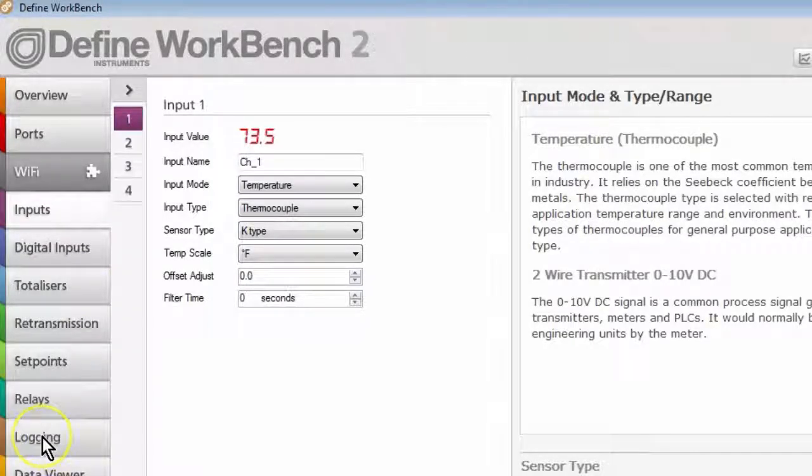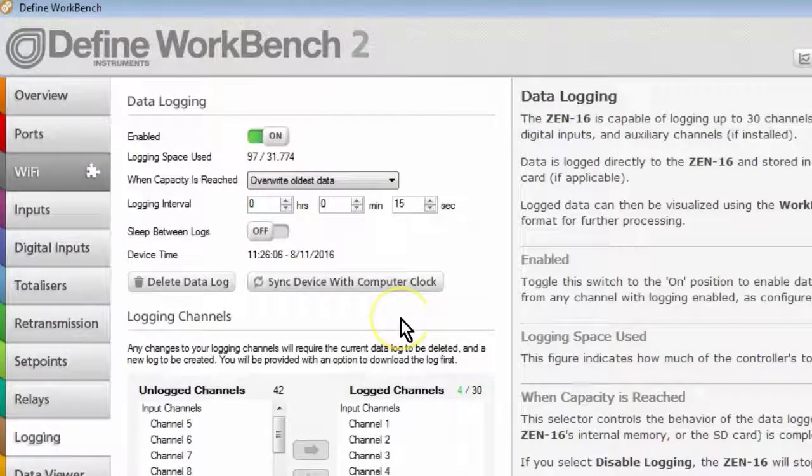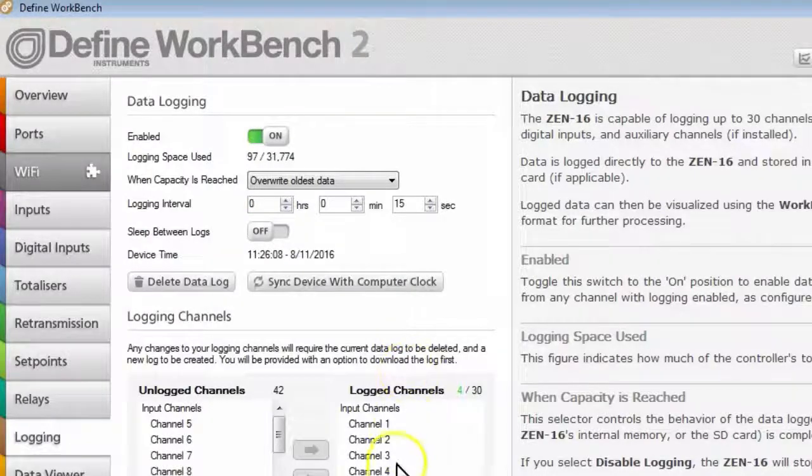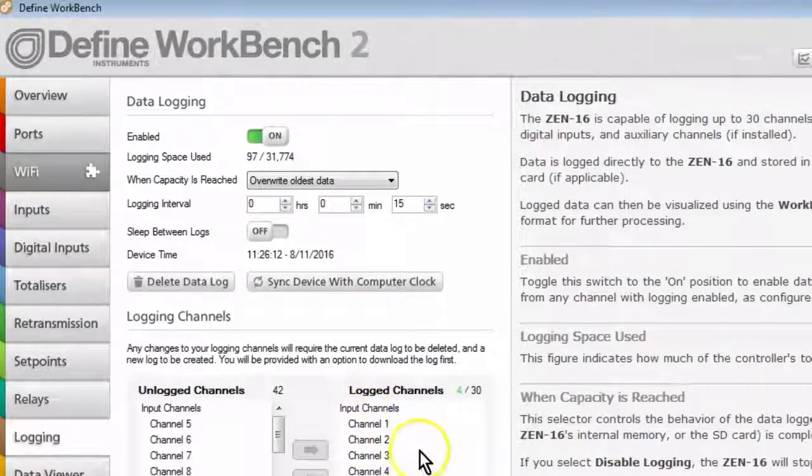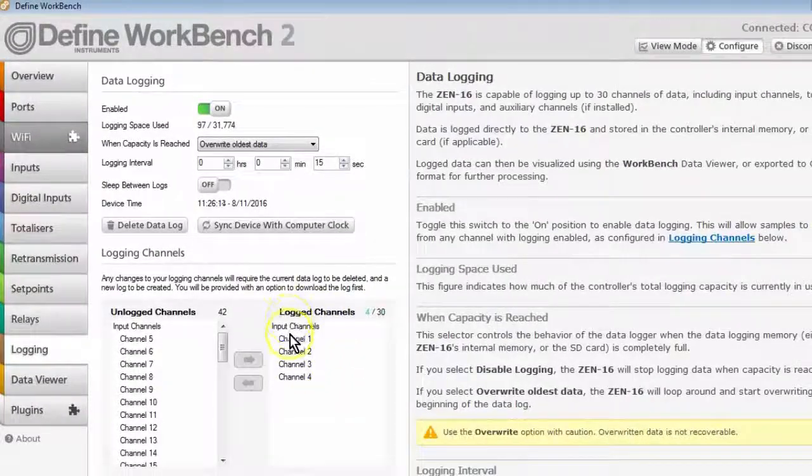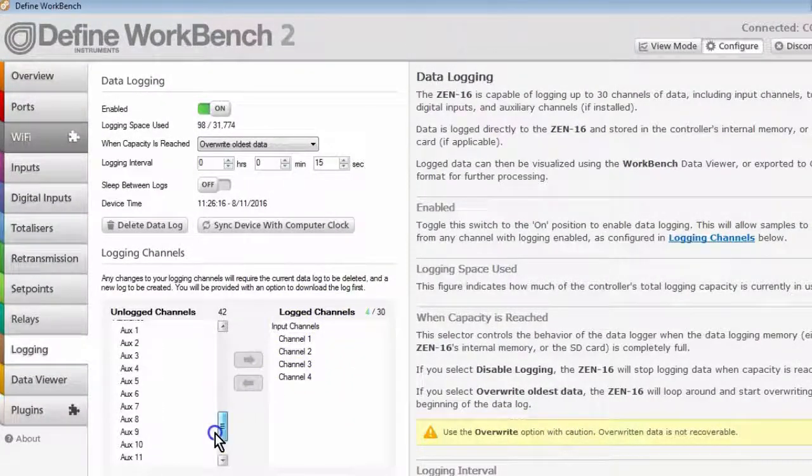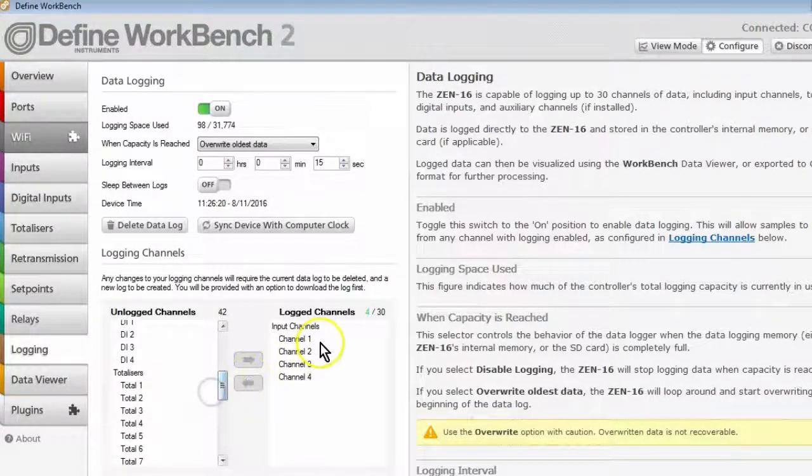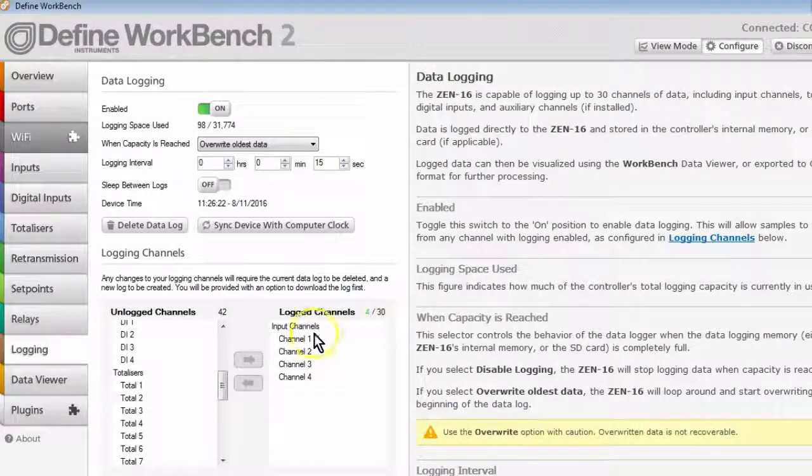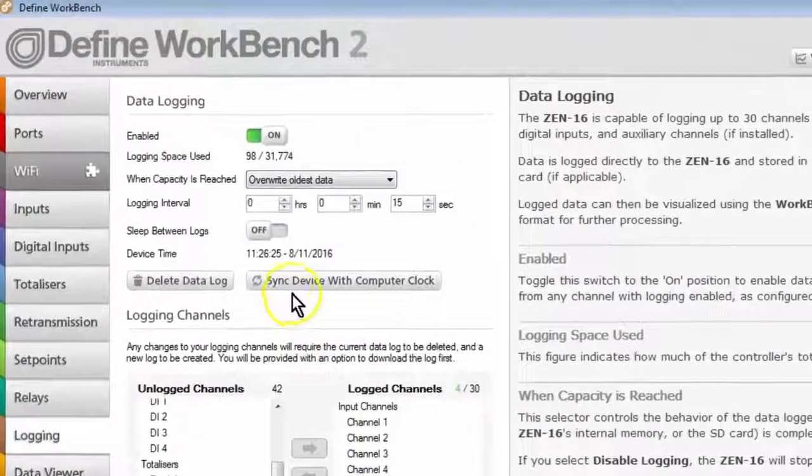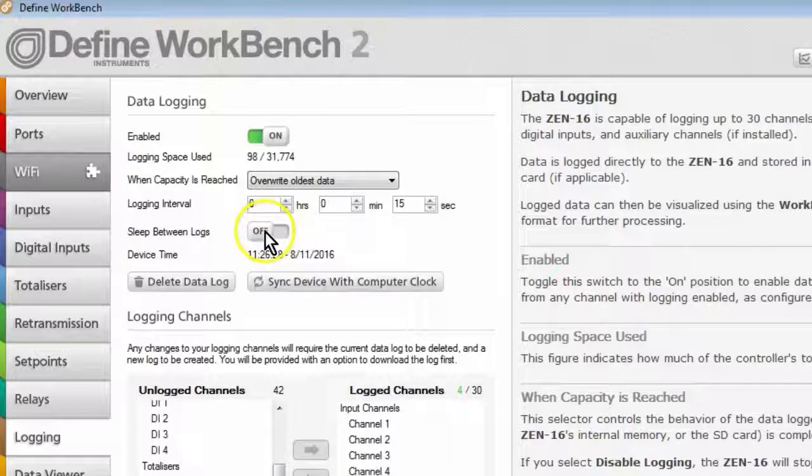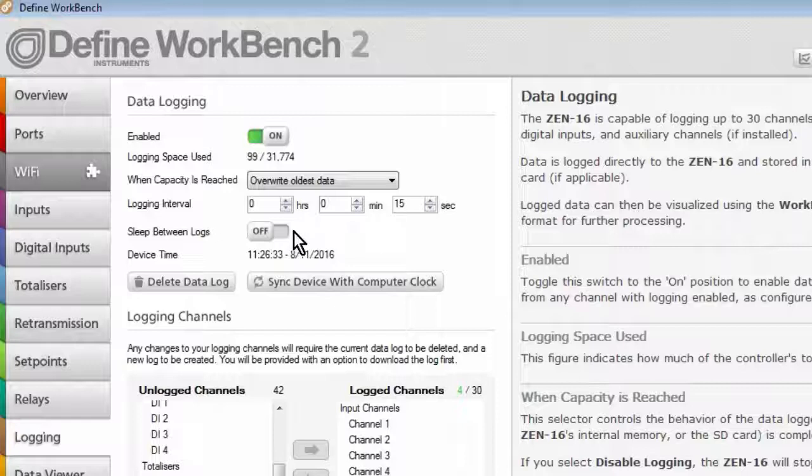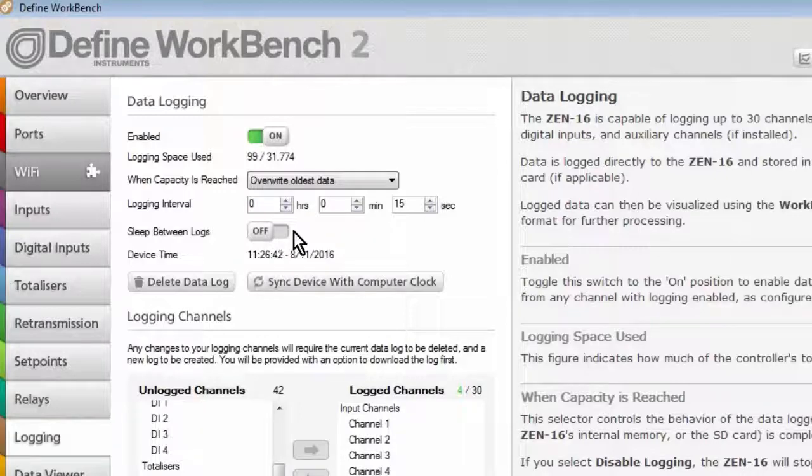Another important thing to check is the logging. Clicking on the logging tab will show you which channels will be published to the cloud. So you can publish any of the channels shown down here on the left. At the moment, for this example, I'm just going to publish the four input channels. Also note the sleep between logs function up here. As mentioned earlier, this allows the device to go to sleep in between log samples and wake up to log, which greatly conserves the power used by the device.